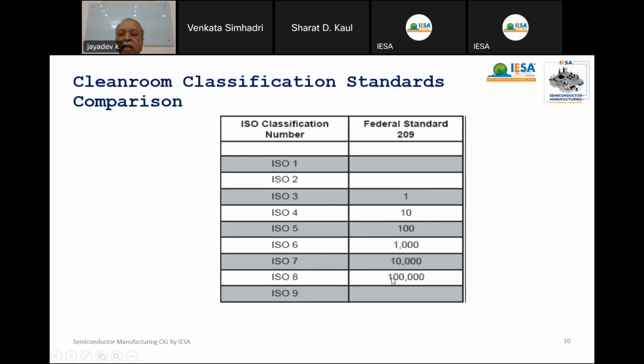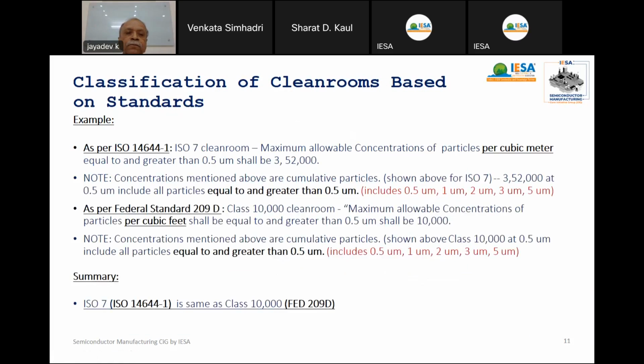ISO 8 means 1 lakh particles. ISO 7 means 10,000 particles. ISO 6 means 1,000 particles. Like this, we can compare this to understand better. So I gave an example for ISO 7. This is nothing but the maximum allowable concentration of particles in 1 cubic meter of 0.5 micron and larger. 0.5 micron and larger particles shall be 3,52,000.